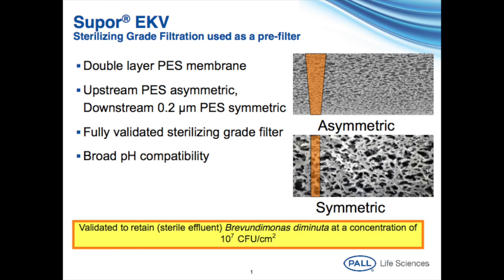What is SUPOR-EKV? SUPOR-EKV is a double-layer polyethersulfone membrane. The upstream layer is asymmetric with a narrowing pore structure as the fluid passes through the membrane. The downstream layer is symmetric with a consistent 0.2 micron-rated pore structure through the membrane.